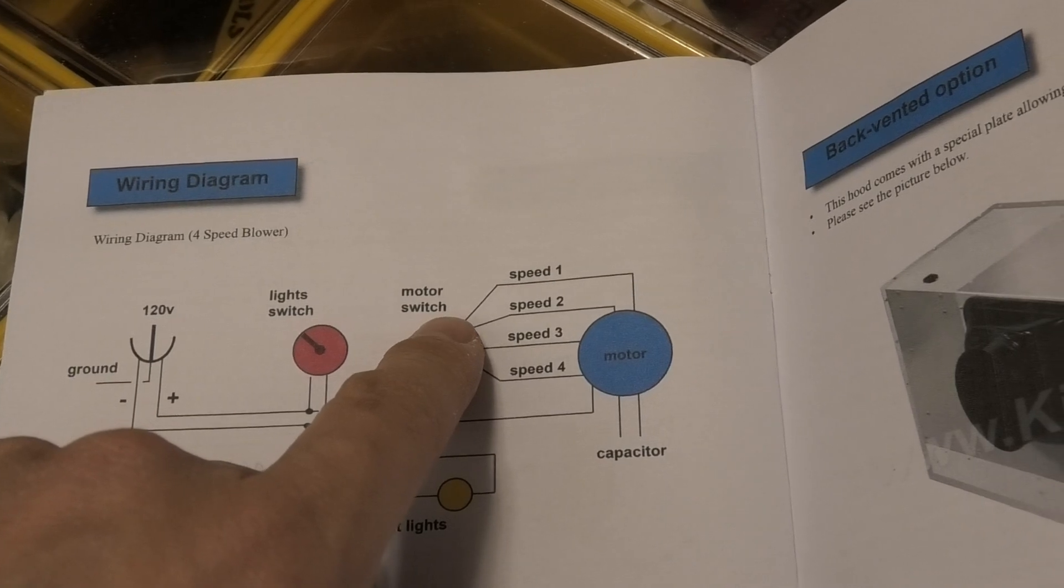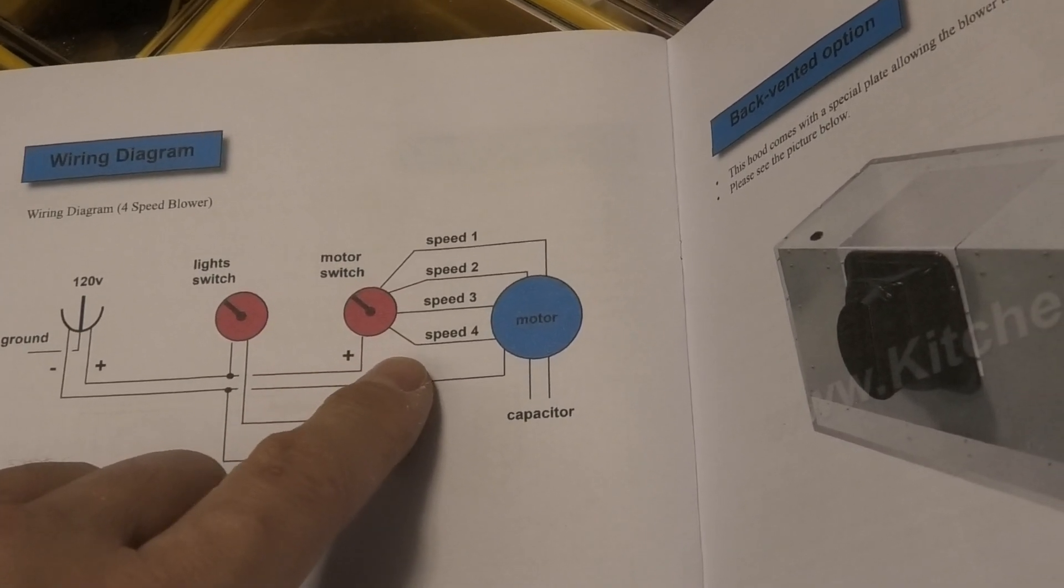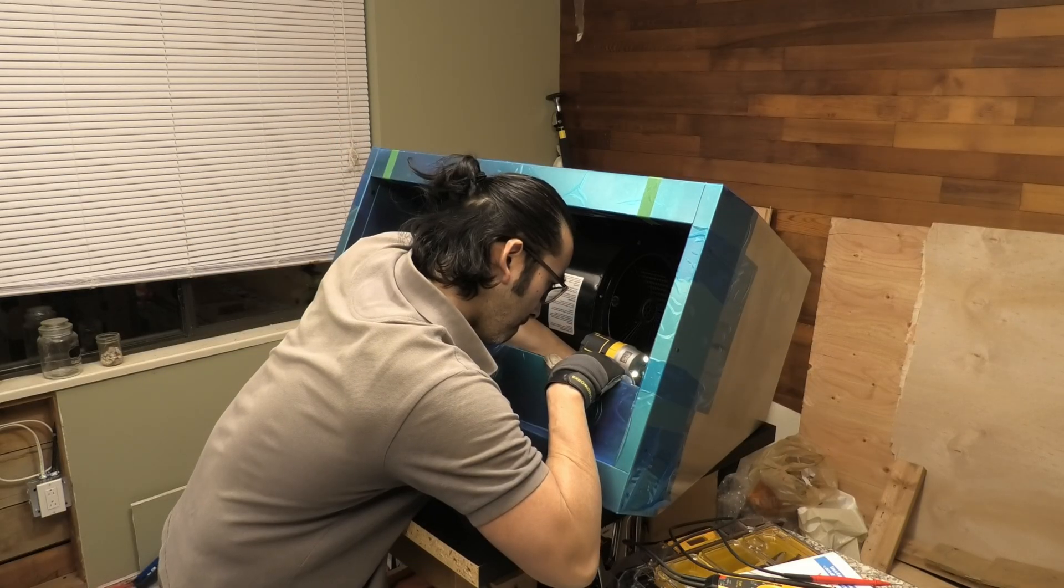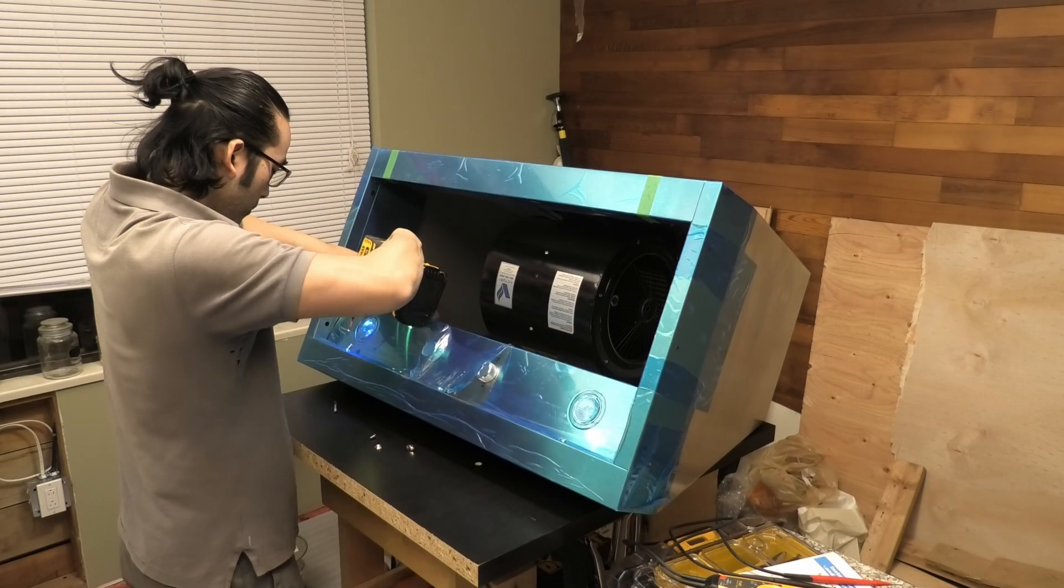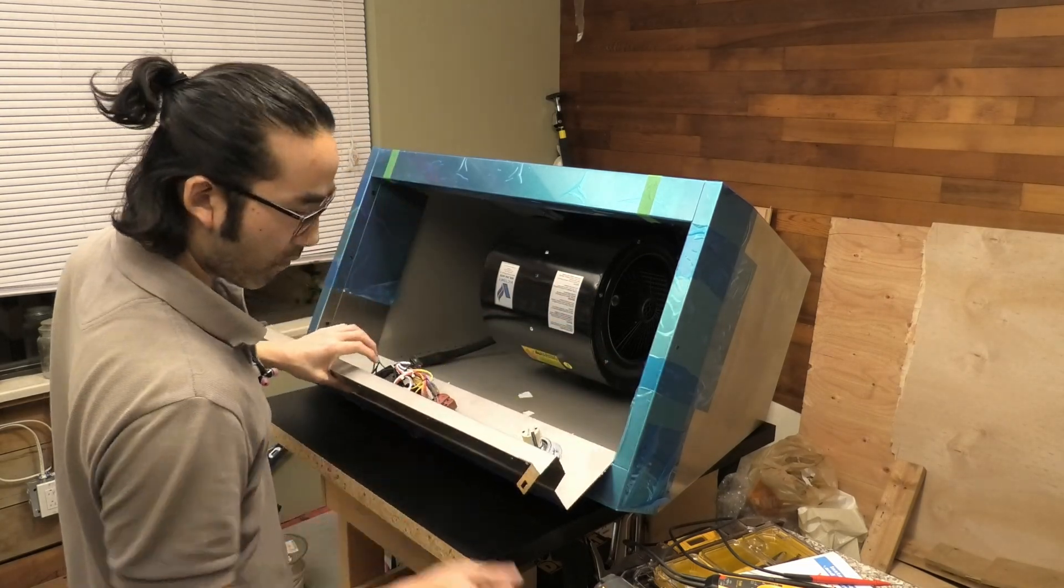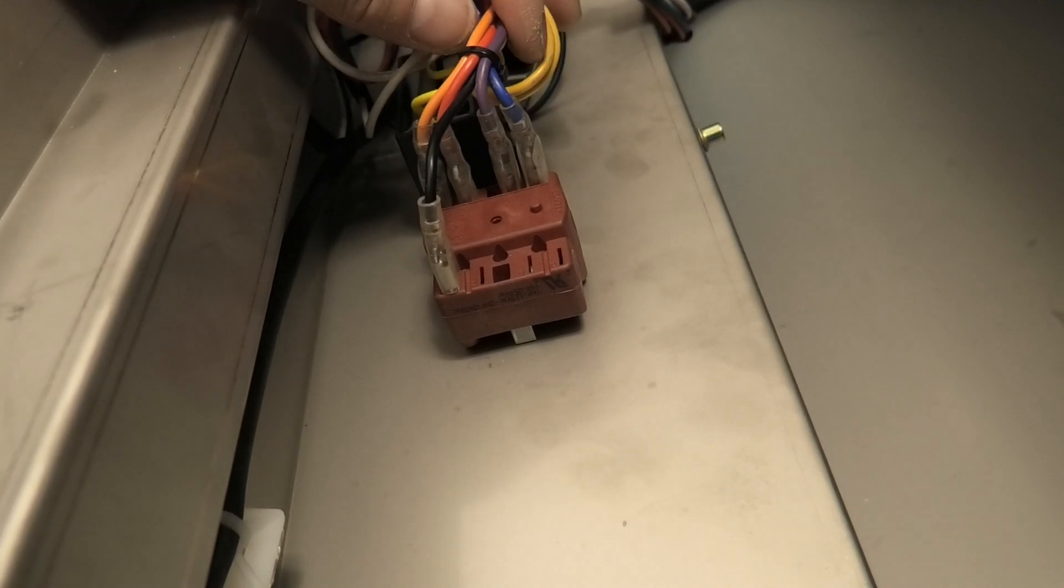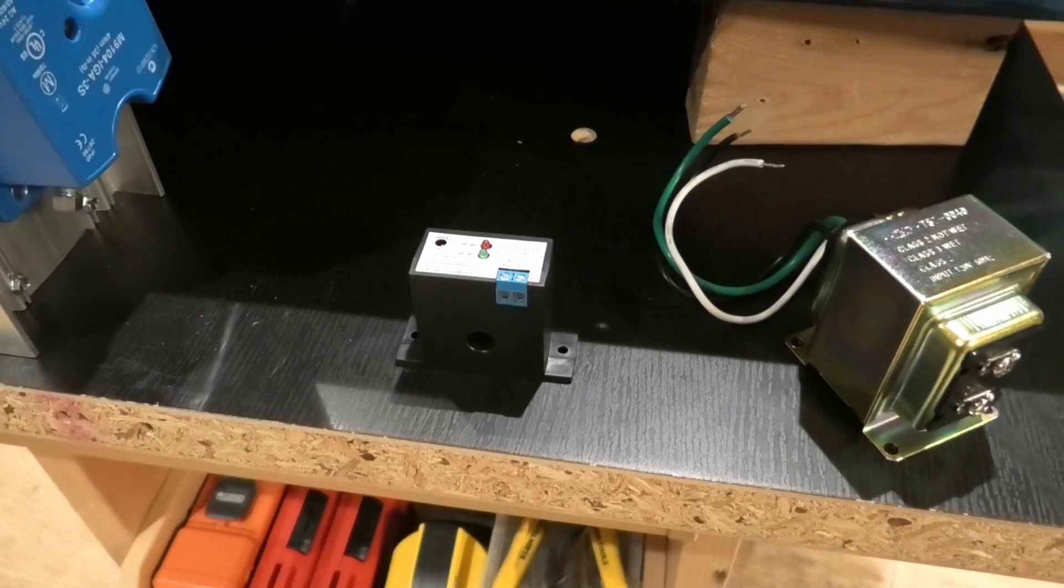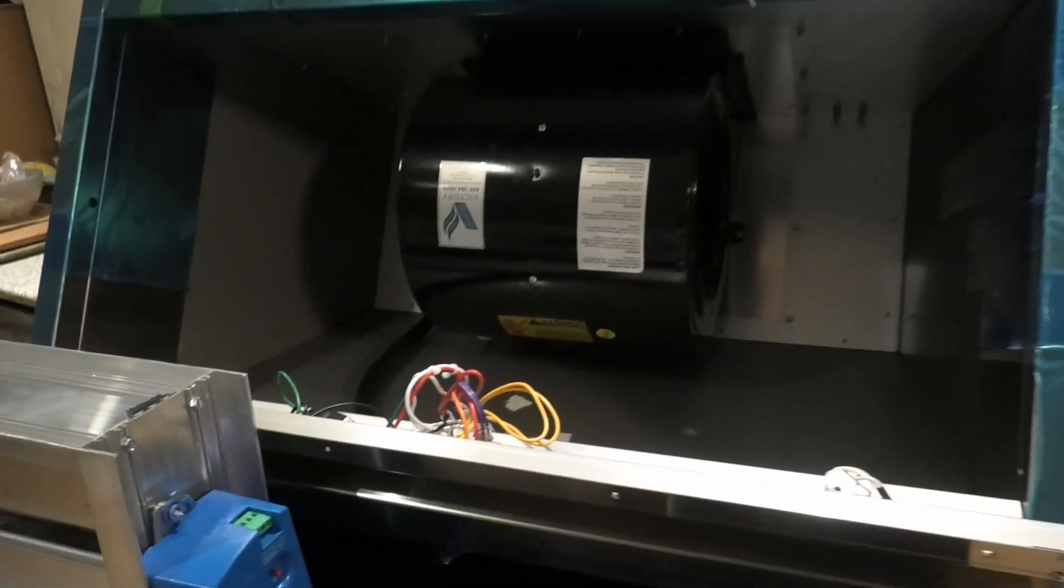So unlike the damper which is normally closed, this switch is normally open. So this motor has four settings. Just for this test, I'm gonna hook up speed two and three through the current sensor switch, and this is so I can use one and four as the control. I don't want the system to activate the instant I turn on the hood. The black stays, the rest need to come off. Transformer, current sensing switch, motorized damper, the hood.